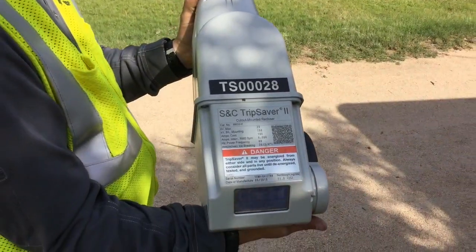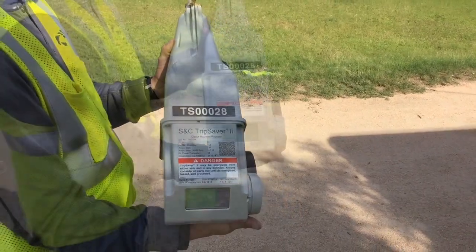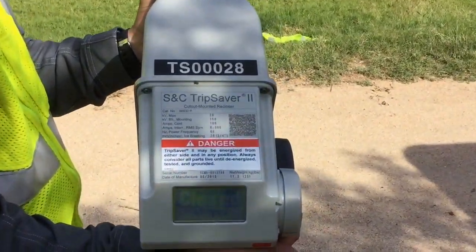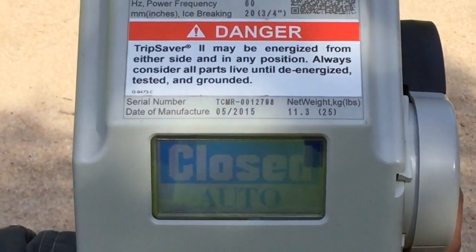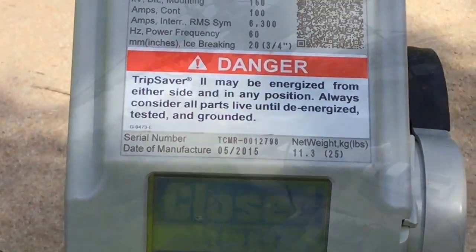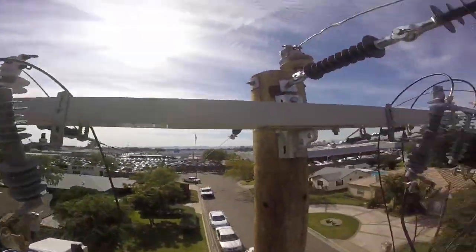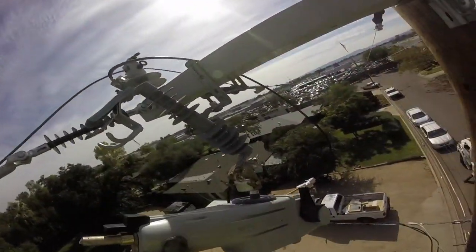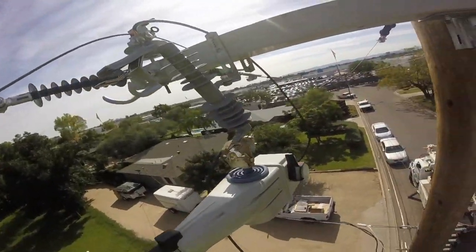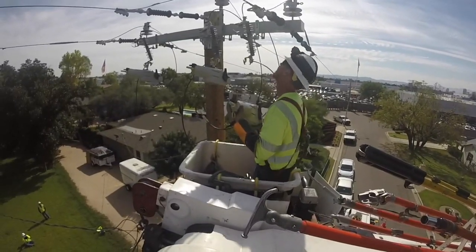This is a good time to take a look at the TripSaver itself, which opens and closes internally in order to isolate phases from a down-lined or faulted condition. Each TripSaver weighs about 25 pounds. Now we're back up in the bucket hanging the first of three TripSavers on this three-phase line, and he's going to verify good closing operation by snapping it up into place before energization.